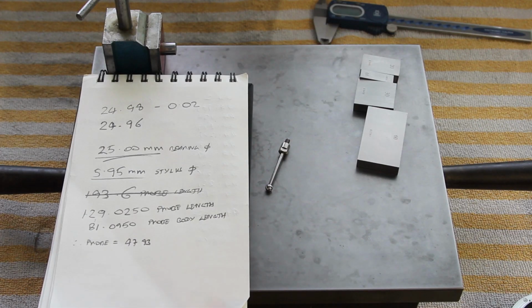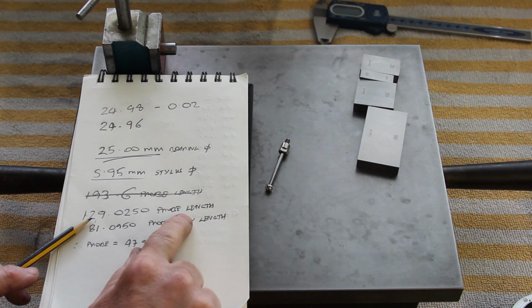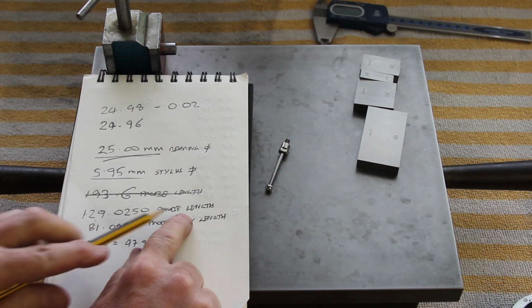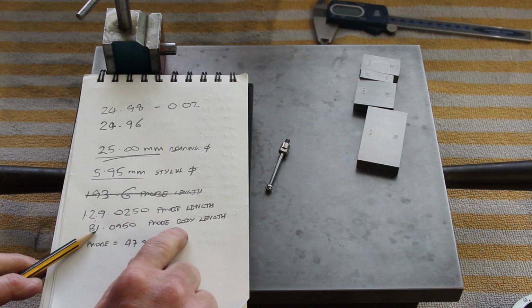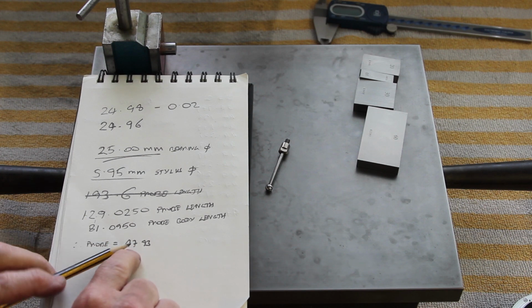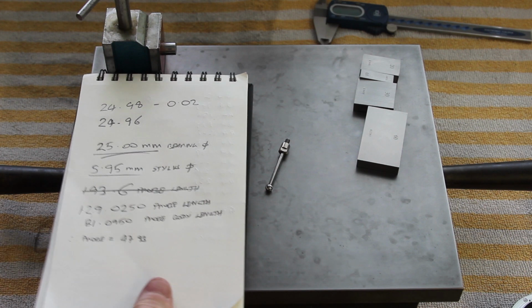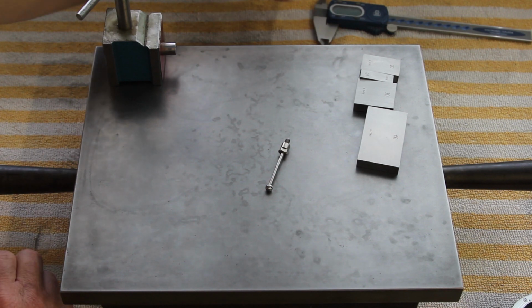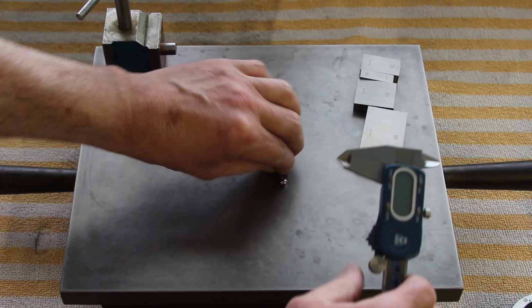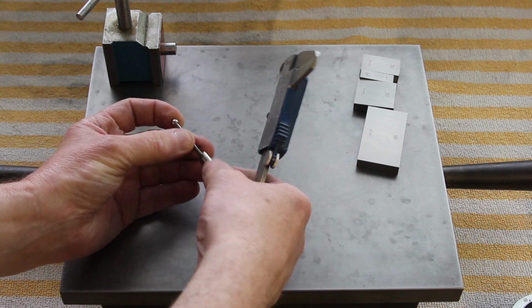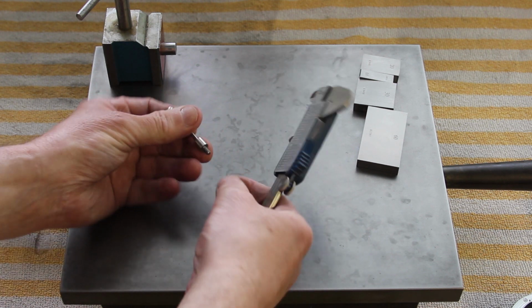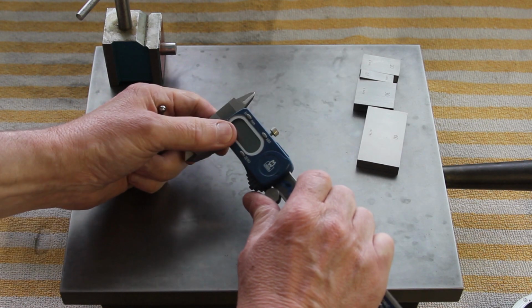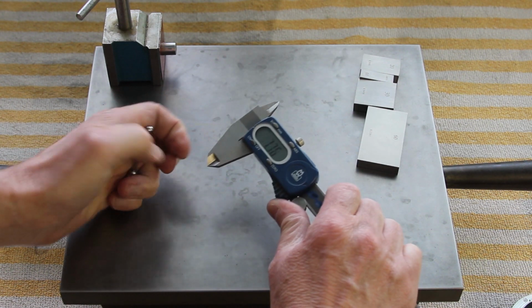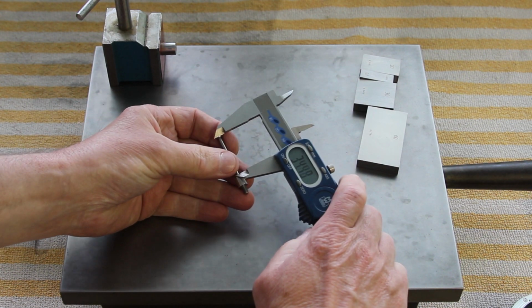That gives me a probe body length of 81.095. Happy with that. So I've got two measurements, the one with the probe with the tip, the stylus screwed in, and one without. So subtracting one from the other, I end up with 47.93. So just as a sanity check, bearing in mind that I can't measure this exactly accurately because I can't measure from the centre of this to the centre of this because the thread's in the way, let's just check with the calipers and see what we get.